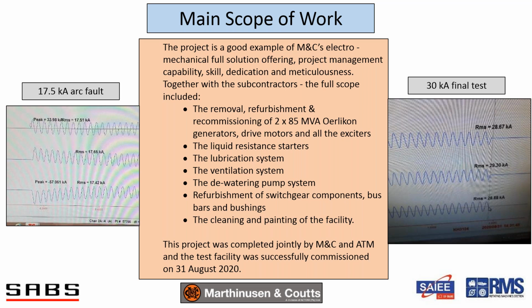Then the liquid resistance starters were fully overhauled on site, as were the lubrication system, the ventilation system, and the dewatering pump system. There was also a refurbishment of switchgear components, bus bars and bushings. And last but certainly not least, the cleaning and painting of the facility. You can see by the photos just how impressive it turned out to be. It was completed by M&C and ATM, and the test facility was successfully commissioned on the 31st of August. Over here, this was the final 30 kA test that was done on the 1st of September.